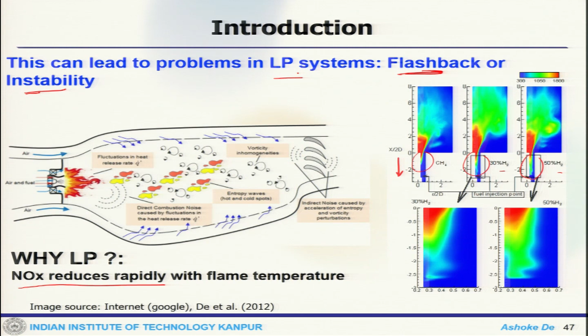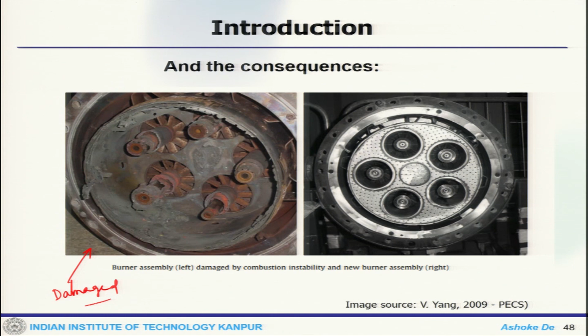So, on one hand one can expect a lean premix system to have better performance and less pollution, but at the same time it becomes more susceptible to flashback or instability. If that kind of situation happens, this is one picture of what happens to the burner assembly. This one is damaged, and this is a new one. It is a nice looking burner setup, but because of this instability or flashback, it has been completely damaged. That is why control or handling of premix flame is not that easy. It has certain issues, and it is quite dangerous too.